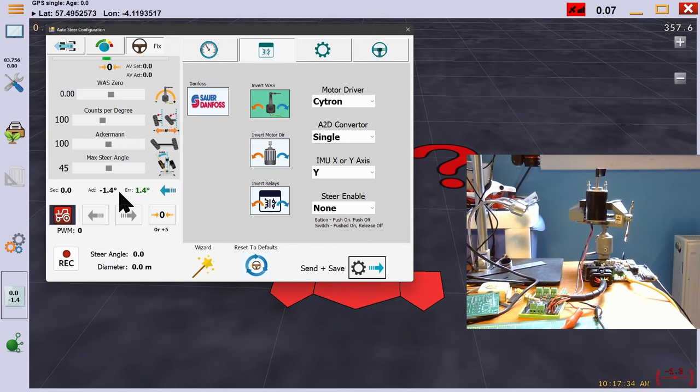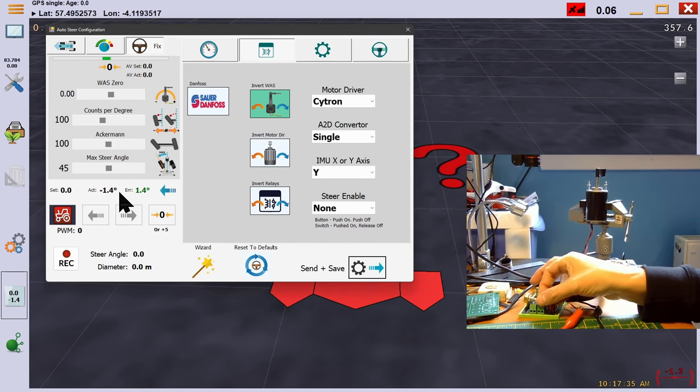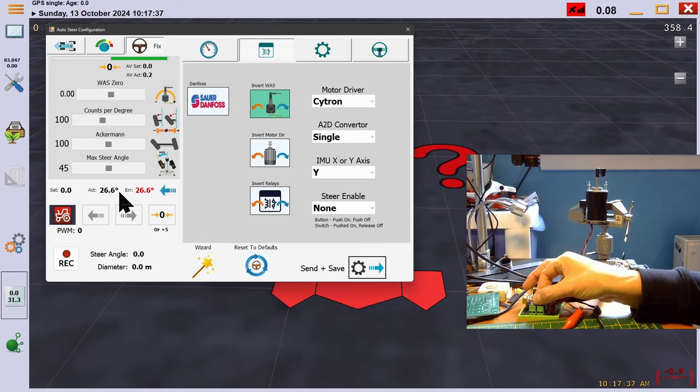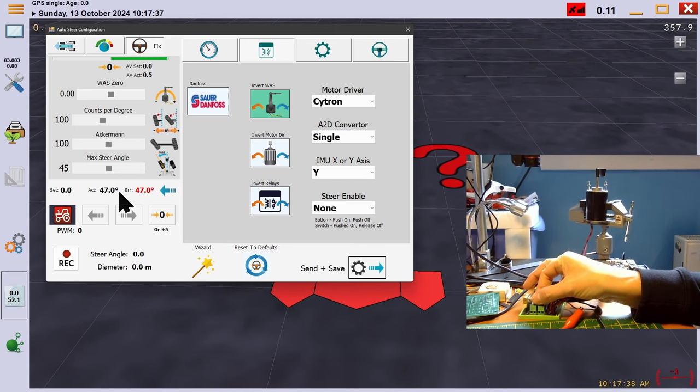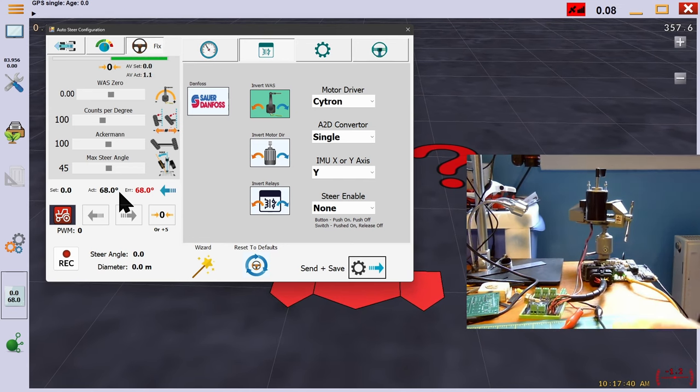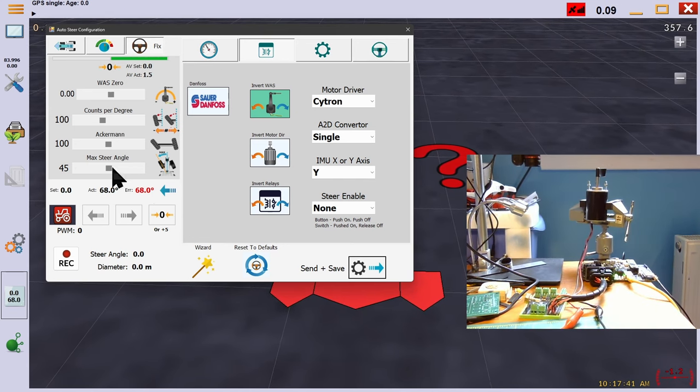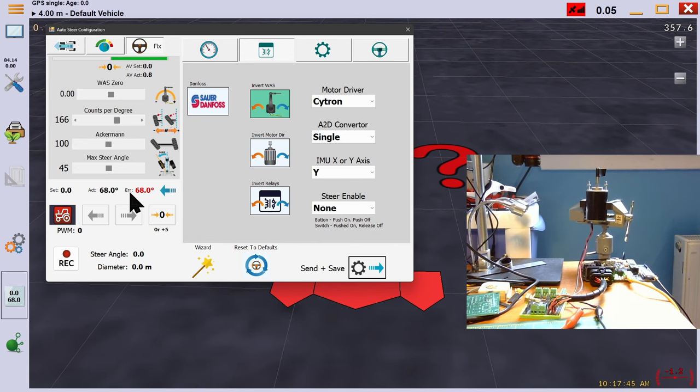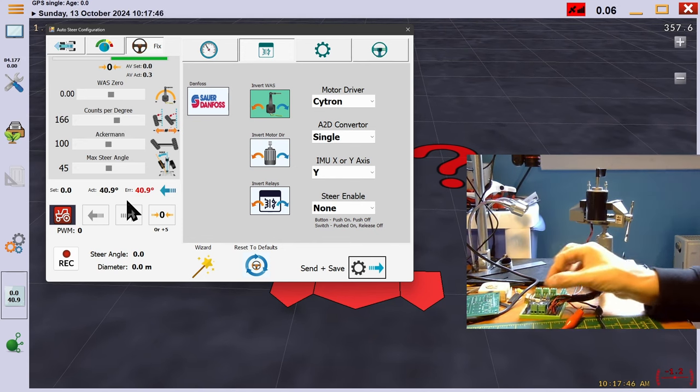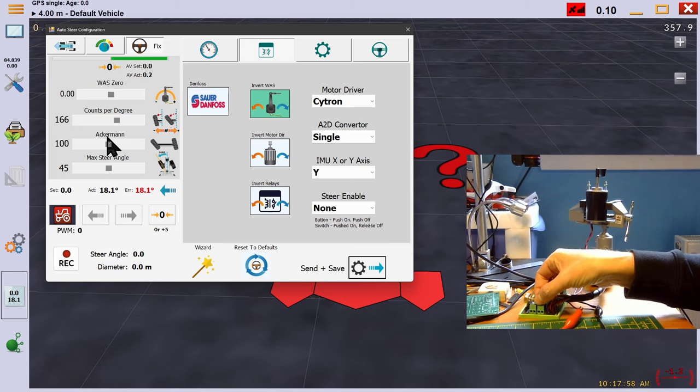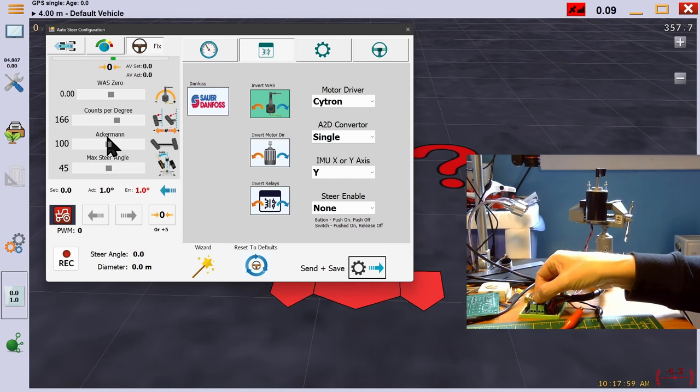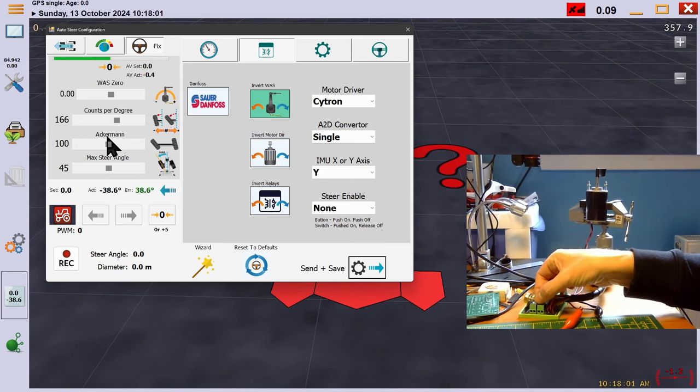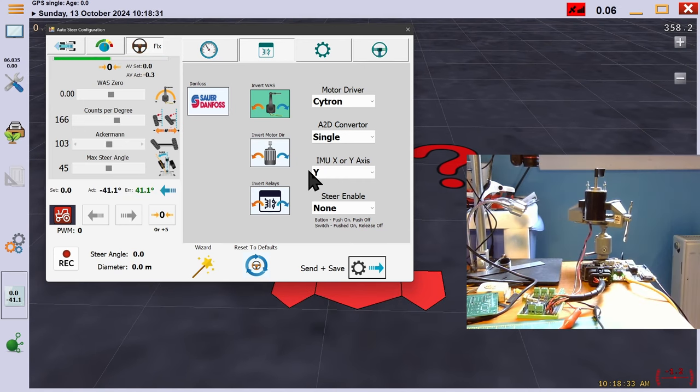Now, we'll turn the sensor all the way to the right, and it reads 68 degrees. We'll aim for a more realistic 40, so we change the CPD until the angle is in that area. Now we turn all the way to the left and tune Ackerman until it reads similar to CPD. We're close enough at 41.1.